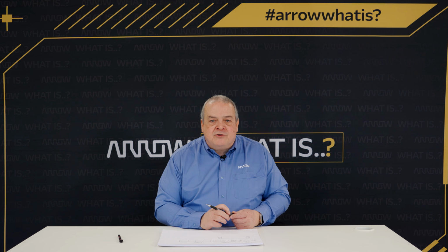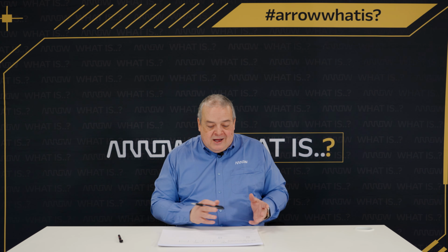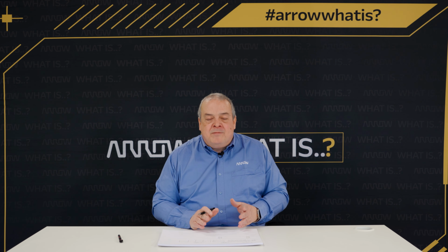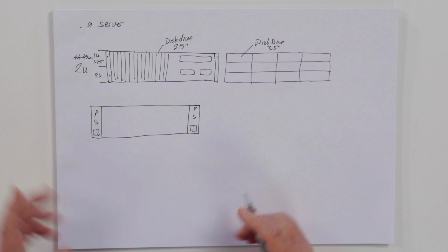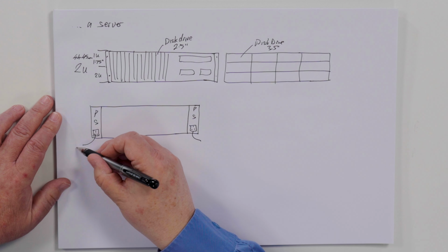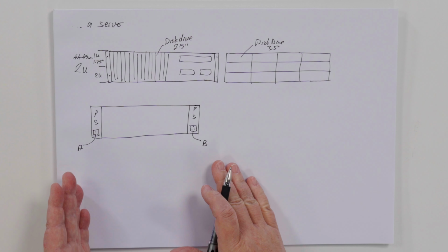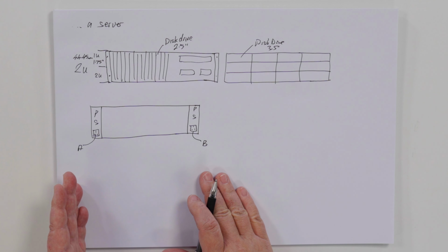The last thing we want to do is to buy a server or storage or networking or build our data center infrastructure and have it fail because we hadn't had a second source of supply, a second network connection, a second disk drive. It's important to make sure that any single component can fail and still maintain the system's operational state. So here you'll see in the back of the server, we have two power supplies. These will be connected to two different power sources. So we have a contingency there in case one of these power sources should fail.